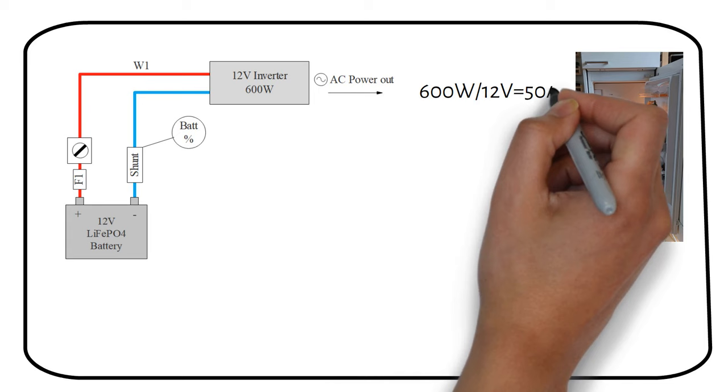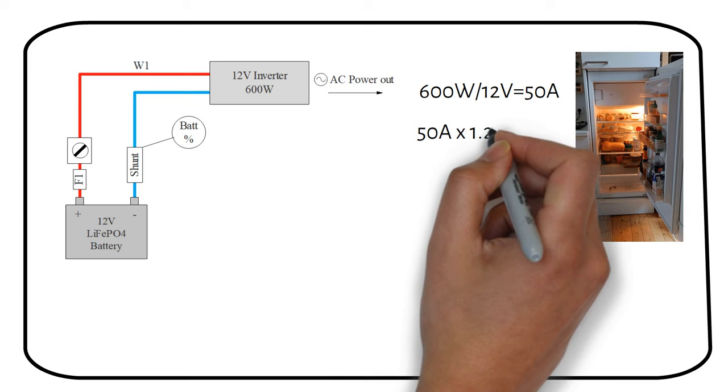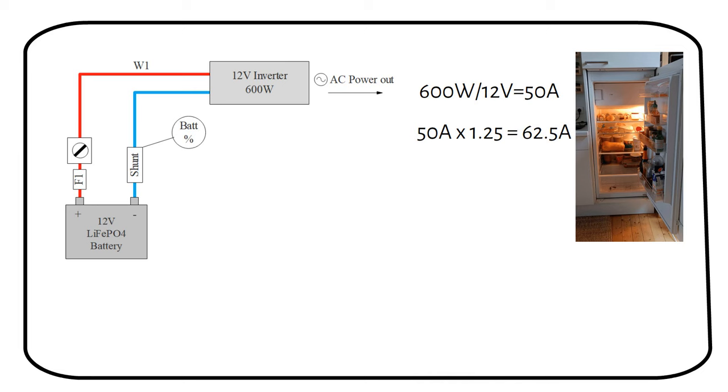Next, we have to apply a safety factor. This is to account for the higher surrounding temperatures. We use a safety factor of 125%. So we multiply the 50 amps by 1.25 to get 62.5 amps. Now that we know the current through the wire, including the safety margin, we must look for a wire that can handle this current.